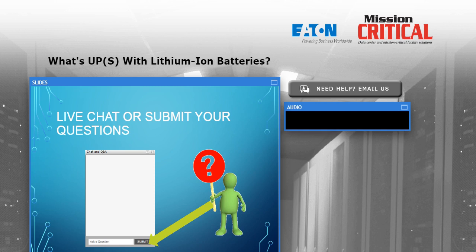Okay, is the BMS a standalone system, or can it be integrated into an existing building automation system? Generally, it's a standalone system. However, all the ones that I've seen on the market have the ability to communicate with the building management system, as simple as via relays, but more likely by an industrial protocol like Modbus or BACnet, the typical types of protocols that you would see in a battery management system. But if all I need is a signal from the battery that says I'm okay, I'm not okay, that could be done with something as simple as relay contact or dry contact signals, and those options exist. I say options, but typically they're standard in every lithium battery system.